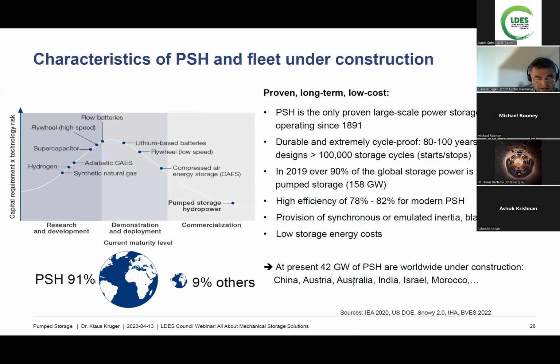Depending on the utilized electrical machines, pumped hydro can also provide synchronous or emulated rotating inertia, which is very important for grid resiliency. So even if a pumped hydro plant is not in turbine mode and not in pump mode, it can rotate in the so-called synchronous condenser mode, with a runner running in air and offering mechanical rotational inertia to the grid.